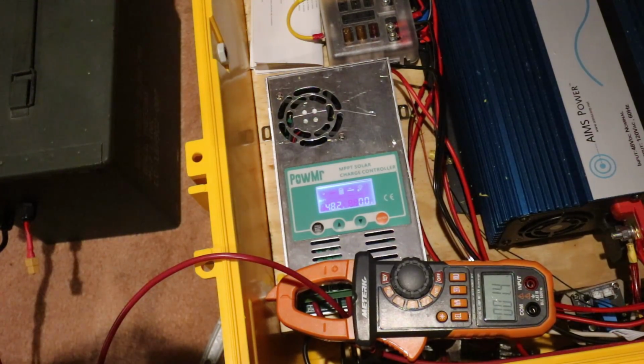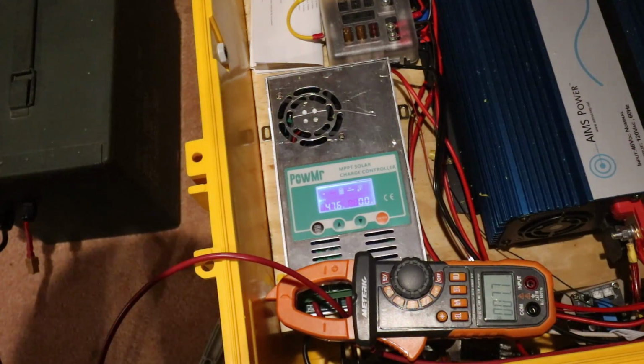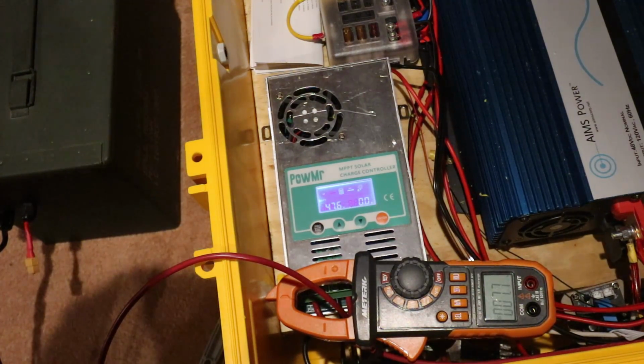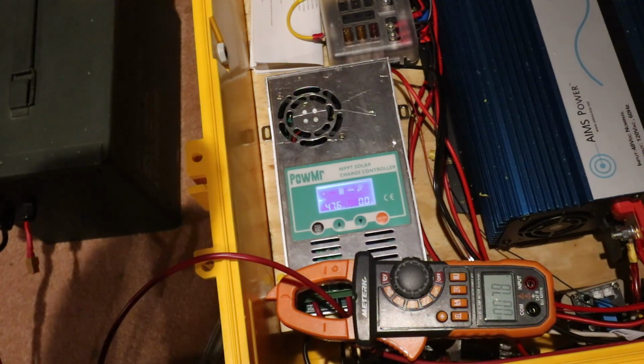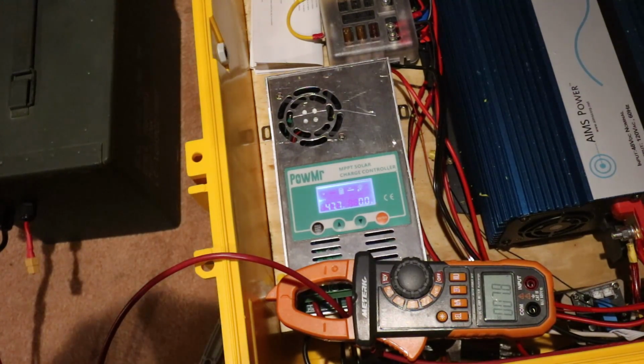When the compressor kicks on, we should kick up into the 10 amp range. There we have it, compressor running, voltage drop wasn't too bad, we're at 7.8 amps. These batteries were right around nominal voltage, which is why we're sitting at about 48 volts, since that's the nominal voltage of a 13S lithium ion pack. So I guess the next thing is I need to capacity test this tomorrow, so I'll plug it in and charge it overnight, and we'll find out what happens tomorrow.